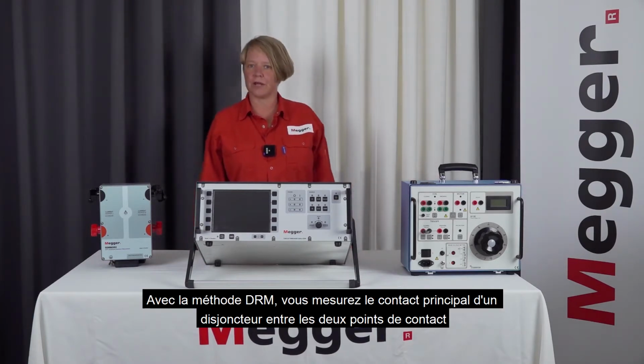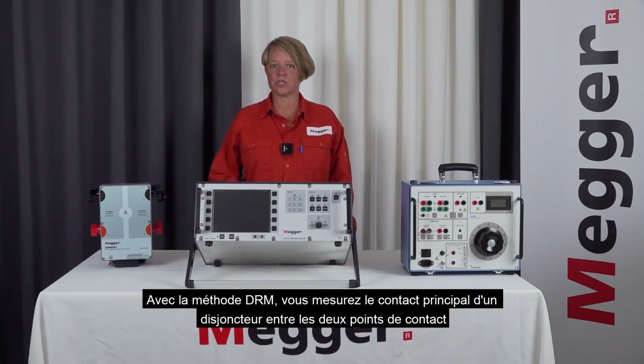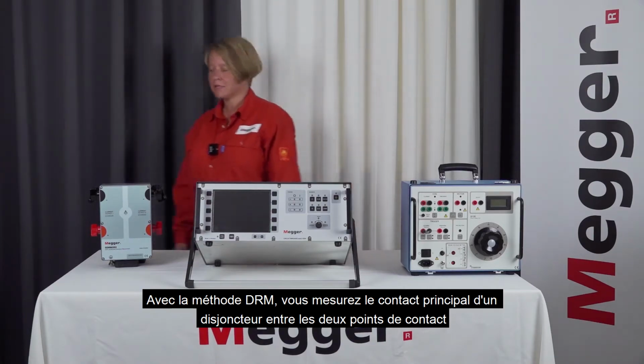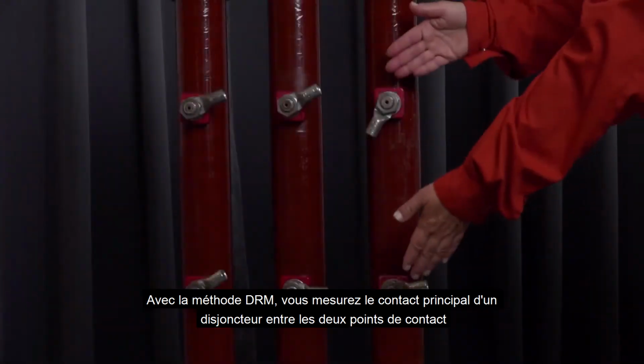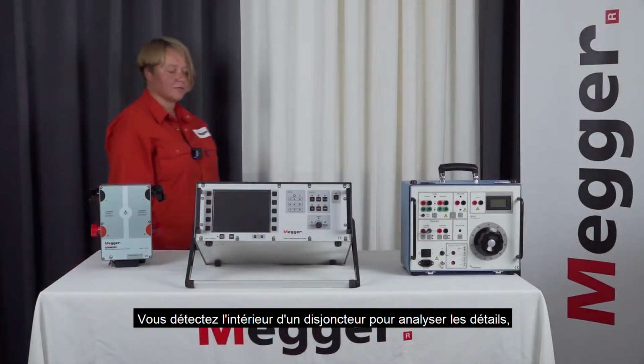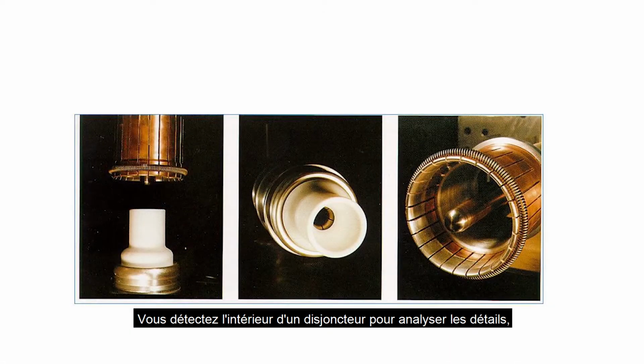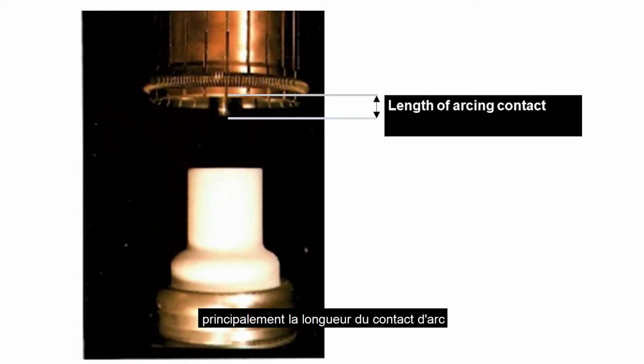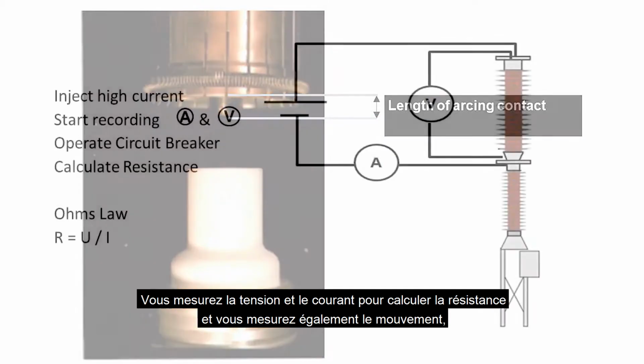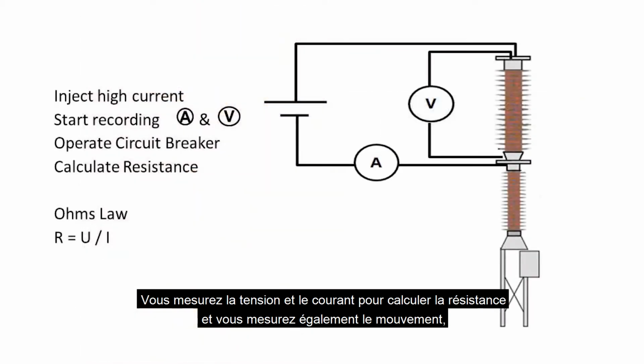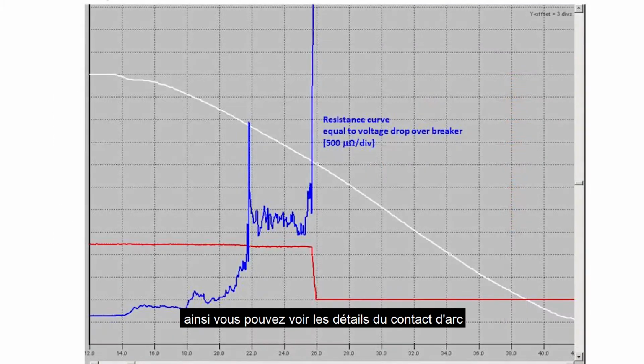The method DRM, you measure on the main contacts of a circuit breaker between the two contact points. You detect the inside of a breaker to analyze the details, mainly the arcing contact length. You measure voltage, current to calculate the resistance, and you also measure the motion. By that you can see details of the arcing contact.